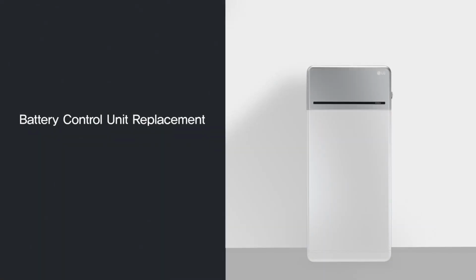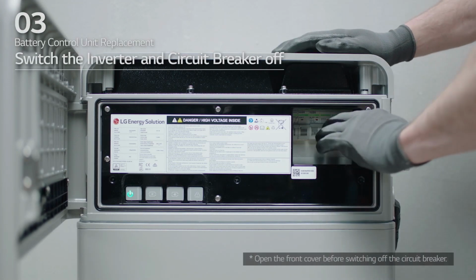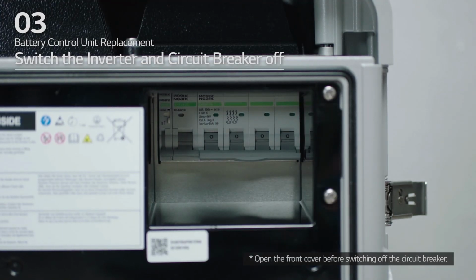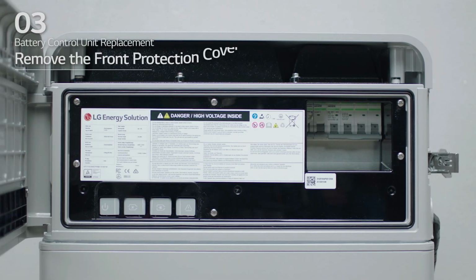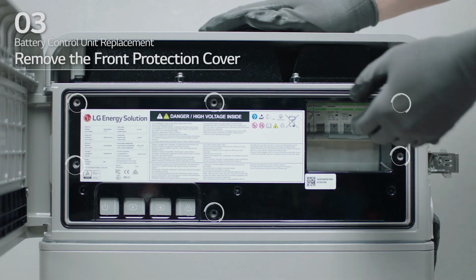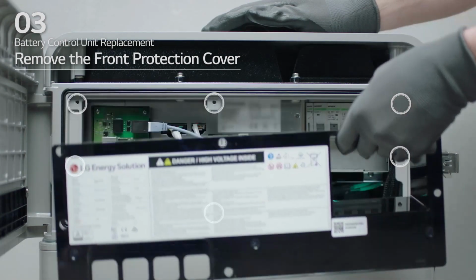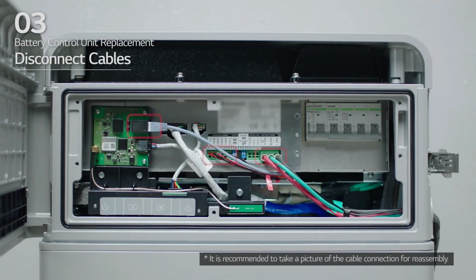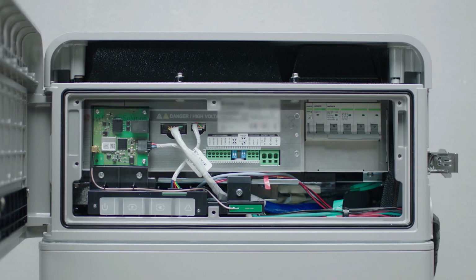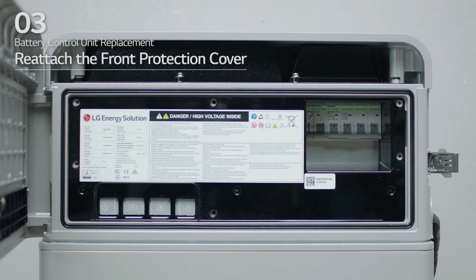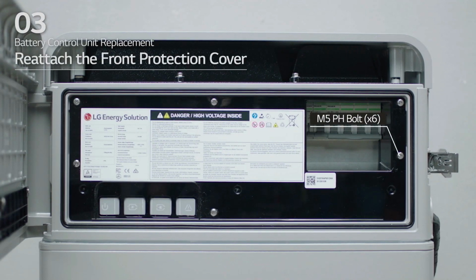3. Battery Control Unit Replacement. First, switch the inverter and circuit breaker off and make sure the switches are in the off position. Then loosen the 6 bolts to remove the front protection cover. Disconnect the cables. Then reattach the front protection cover with 6 M5 PH bolts.